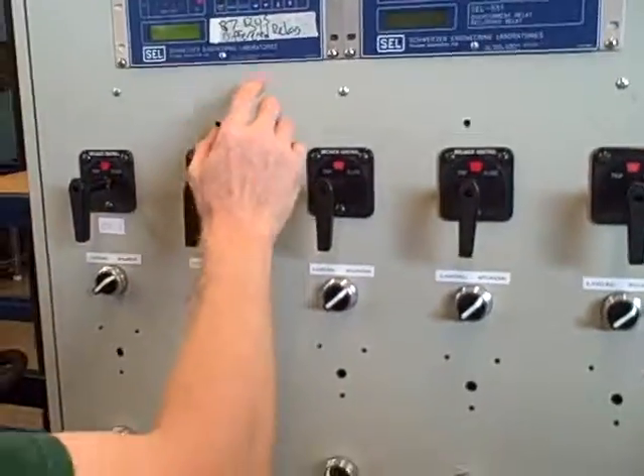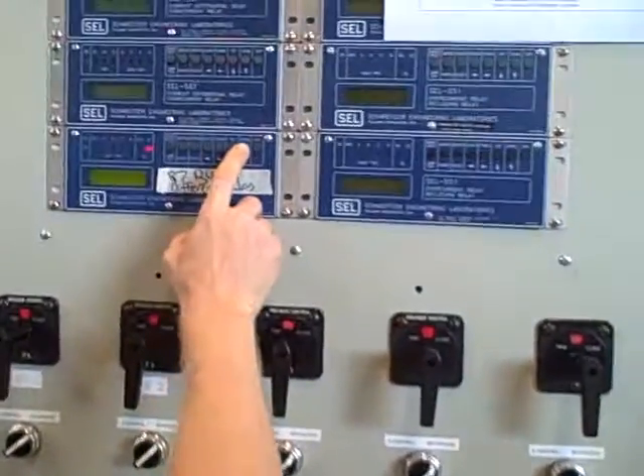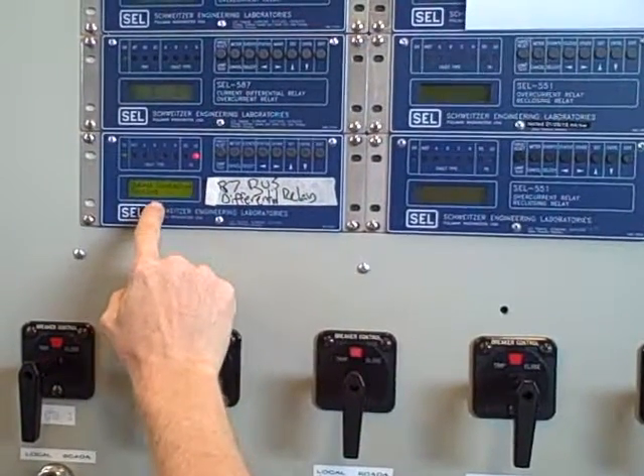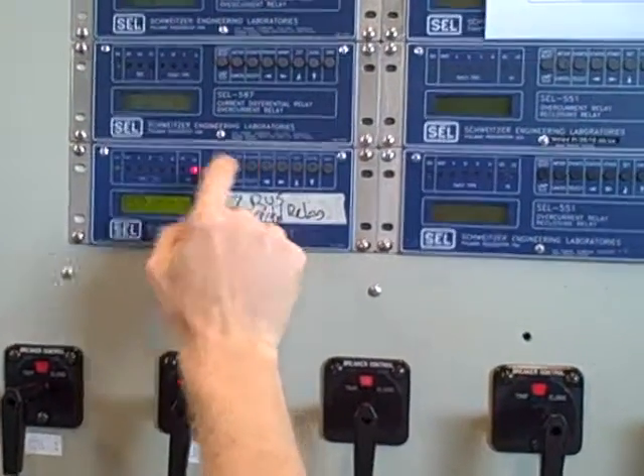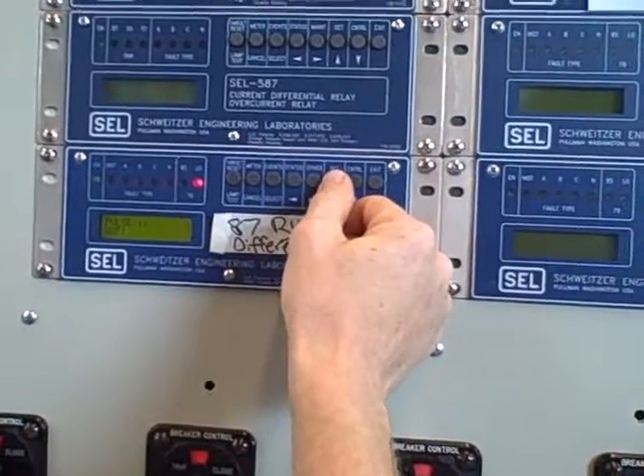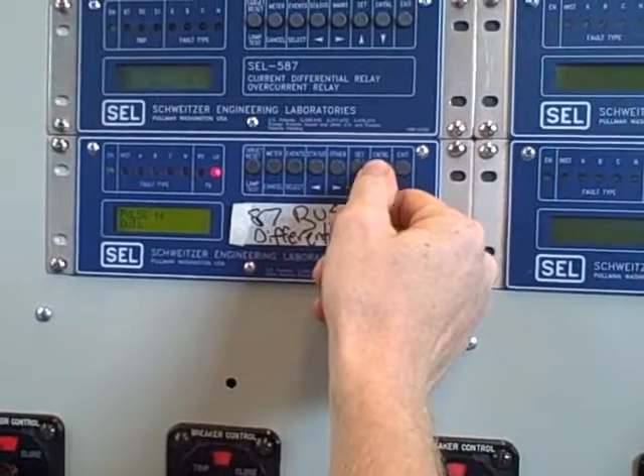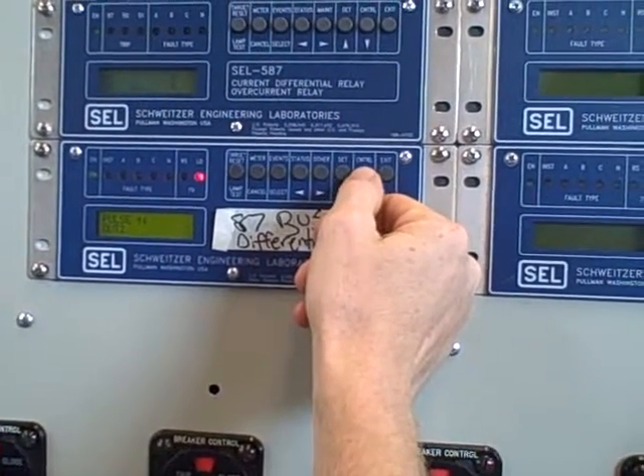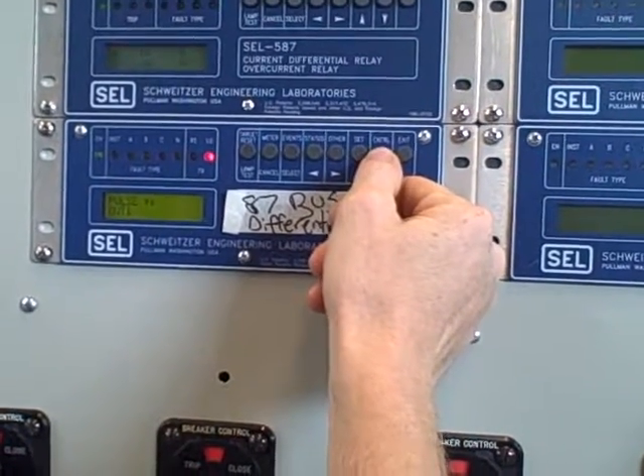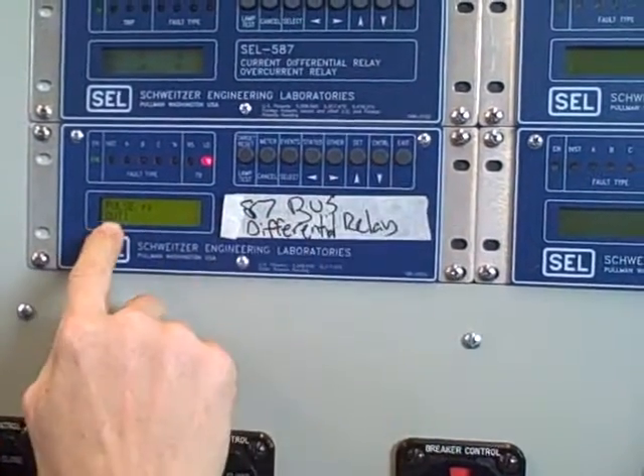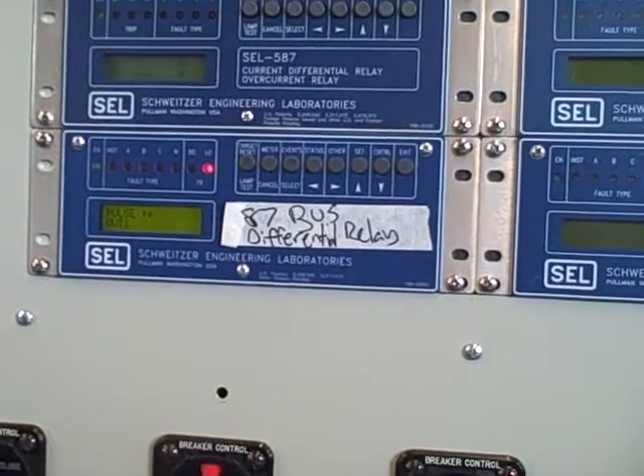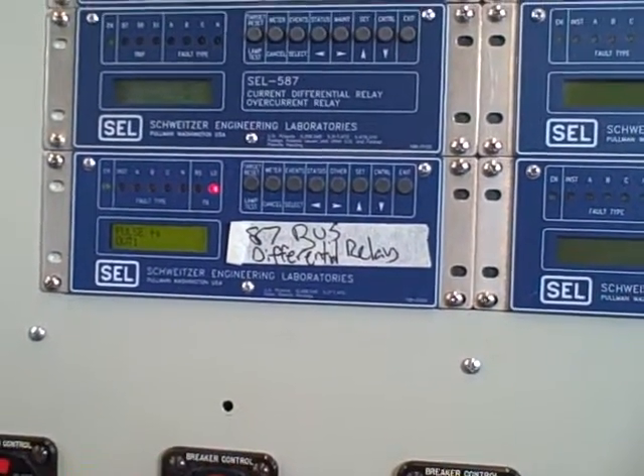Going in here I push the control button — output contact testing. I say yes, I want to do that, and then at this point I can select different output contacts: output one, output two, output three, output four, alarm, and it rolls back to output one. Output one is the contact that runs to our 86 relay to trip it, so that is the one I'm going to pulse.